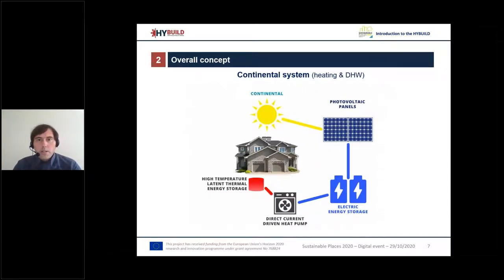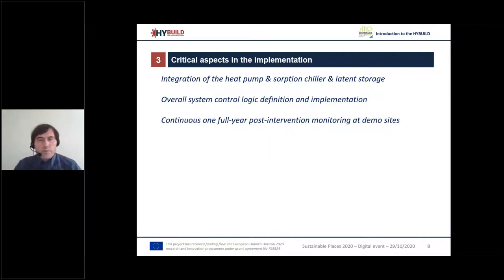With regards to the continental system, which is mainly aimed to produce heating and domestic hot water, there is also a heat pump driven from a DC bus connected to PV panels and electric storage. At the compressor exit, where the hot refrigerant comes out from the heat pump, the sensible part of this energy is used to charge a high temperature latent storage at around 65 degrees C. This energy is then used to supply domestic hot water when needed, or at least to help in its production.